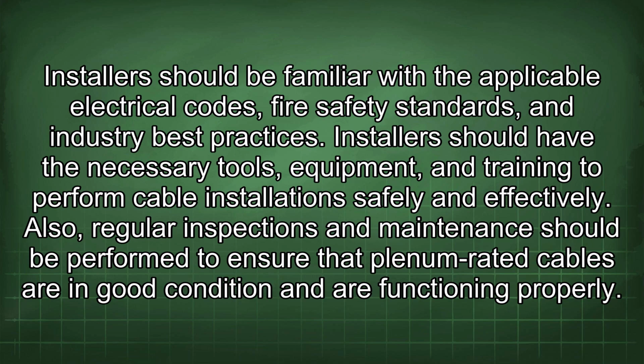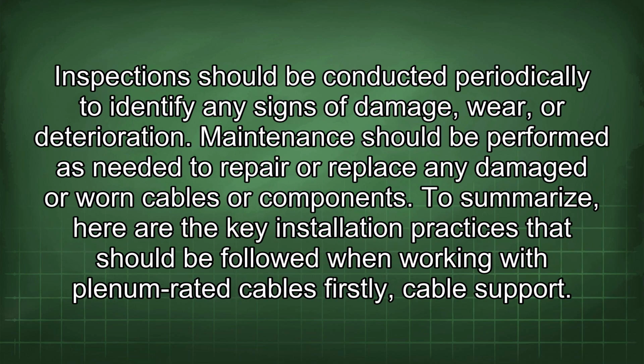Also, regular inspections and maintenance should be performed to ensure that plenum-rated cables are in good condition and are functioning properly. Inspections should be conducted periodically to identify any signs of damage, wear, or deterioration. Maintenance should be performed as needed to repair or replace any damaged or worn cables or components.